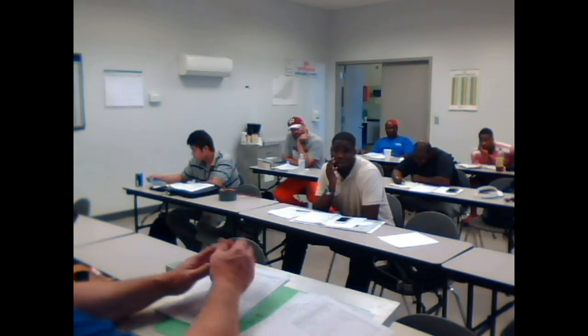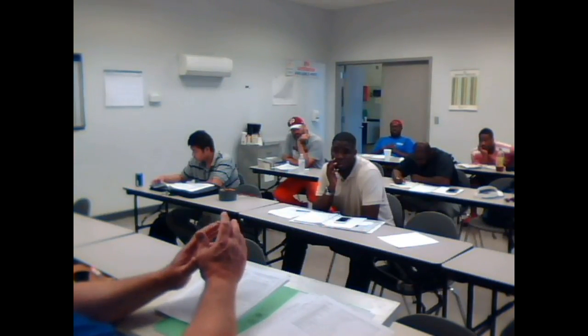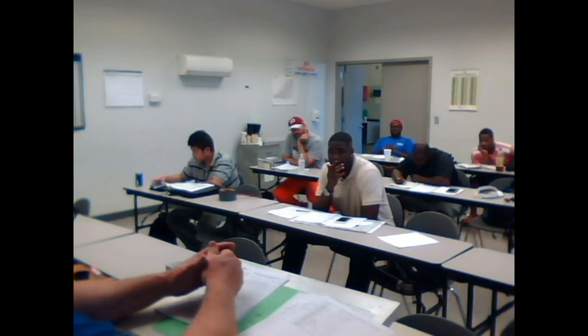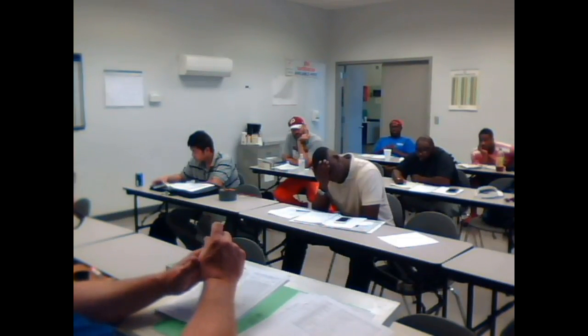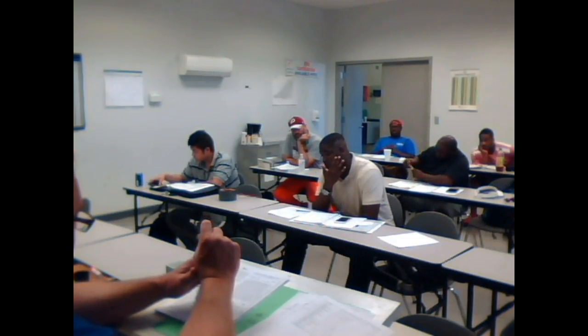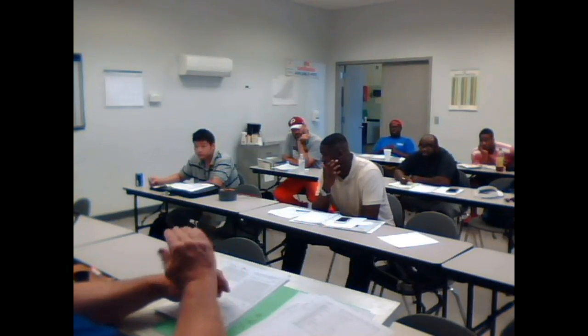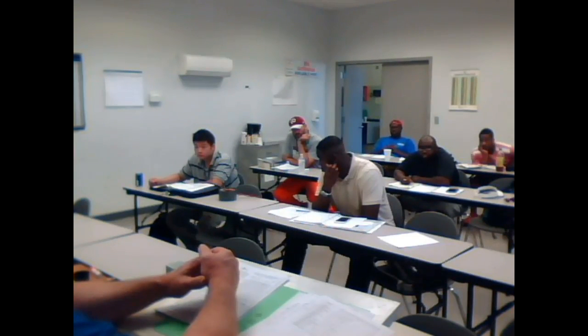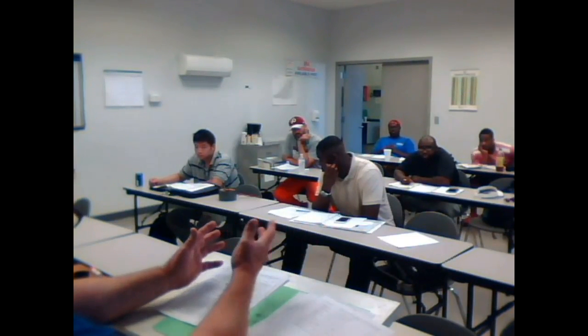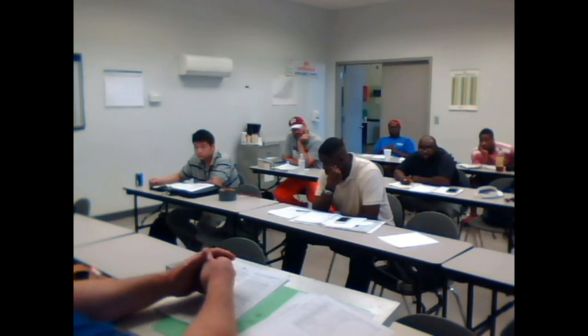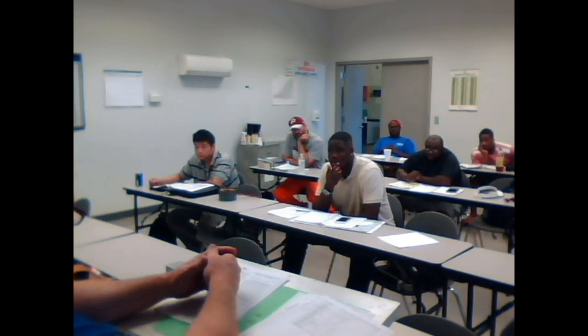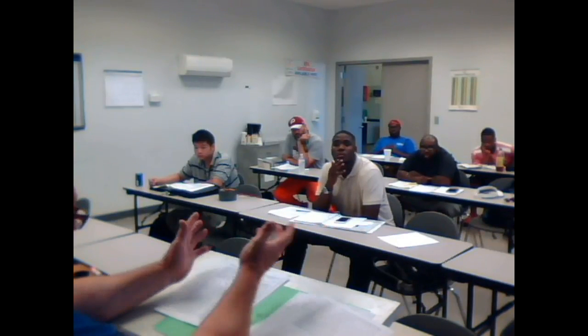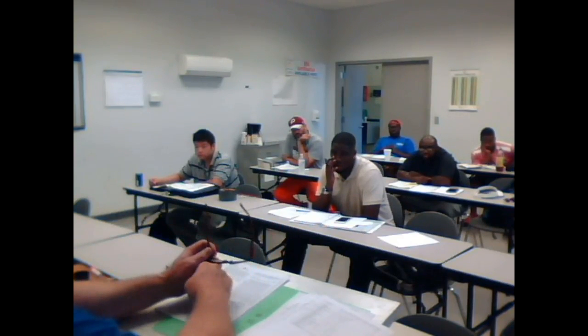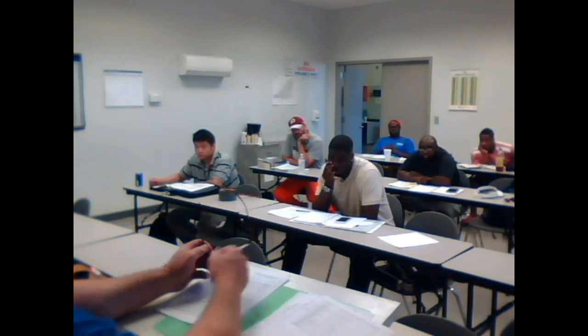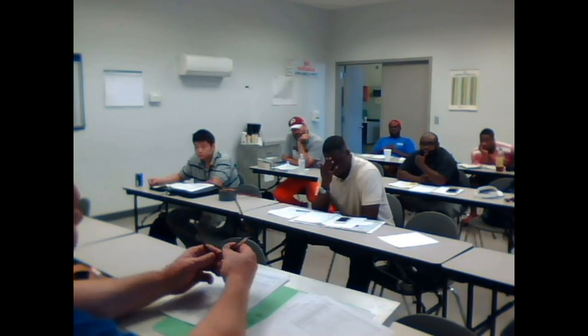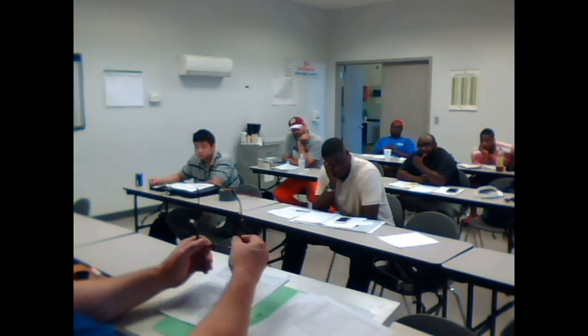I've been on plenty of calls where the contacts are welded shut together. They didn't shut cleanly. They chattered. We got enough amperage, enough current running through them that it just glazed them over and they stuck. So then it ran all the time, and the inside unit would be satisfied, so the inside blower motor would cut off and it would keep running without a fan, so it would freeze up the coil. It's the same way, though not as often, with the blower motor. Remember, if we're using a blower motor relay, then we're saying it's less than 20 amps. There's less power there to burn up those contacts.